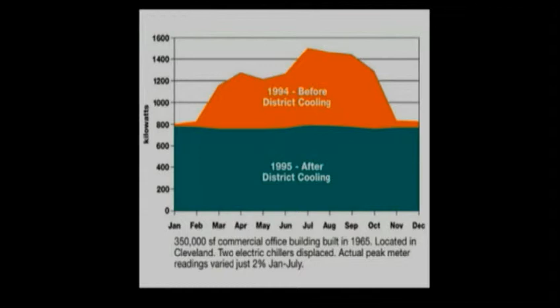This is not a Princeton building, but essentially what happens when a building is on a district cooling loop: the orange is the peak demand in the building, the orange is before chilled water, and the green is after district cooling. If you're an electric utility, the orange part is the bad cholesterol - that's the expensive power. The green is really the type of load you want in all your buildings. So district cooling essentially provides tremendous benefit to the grid.